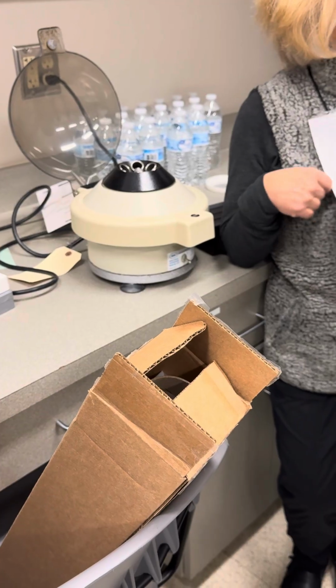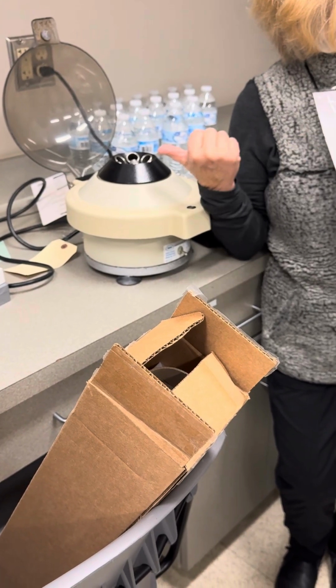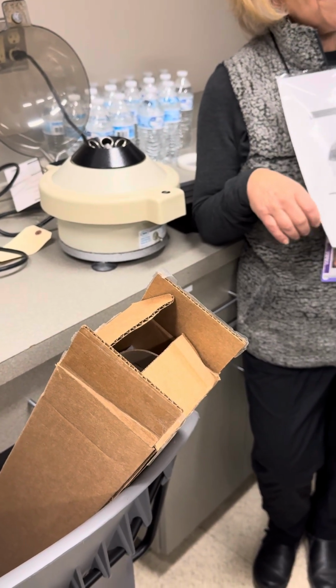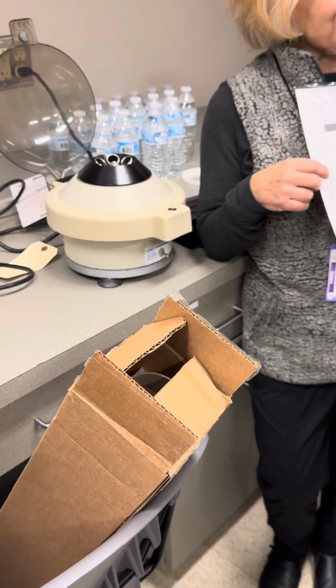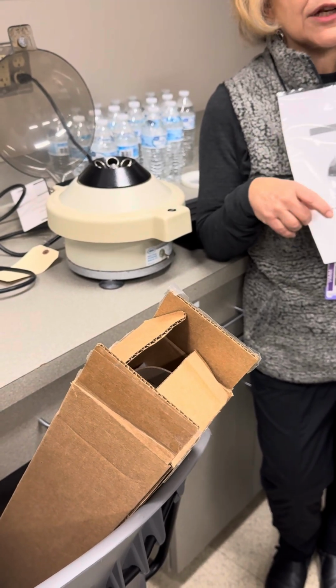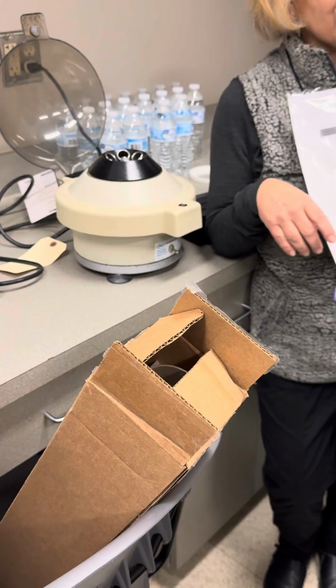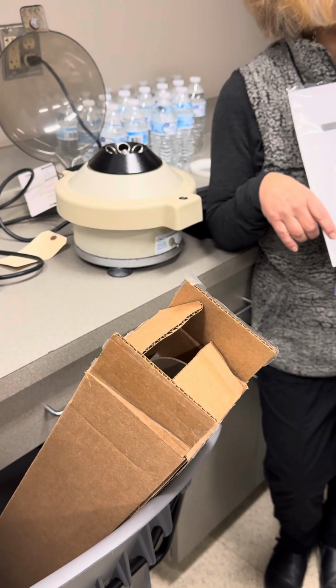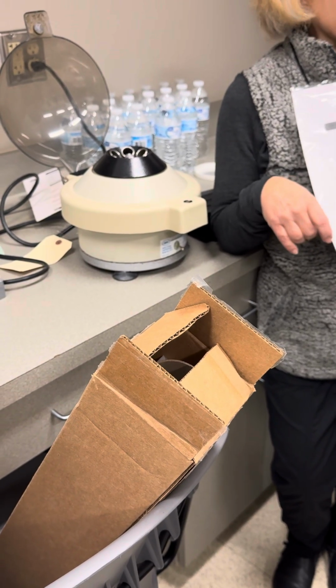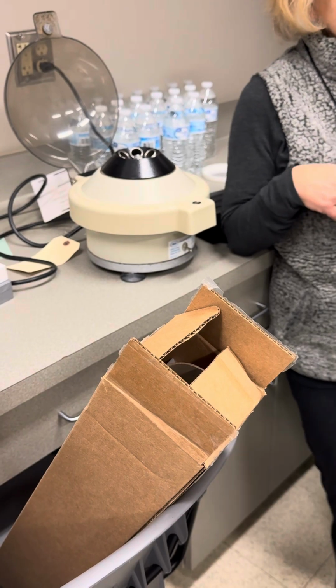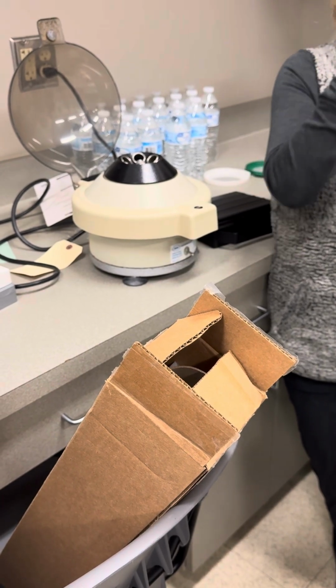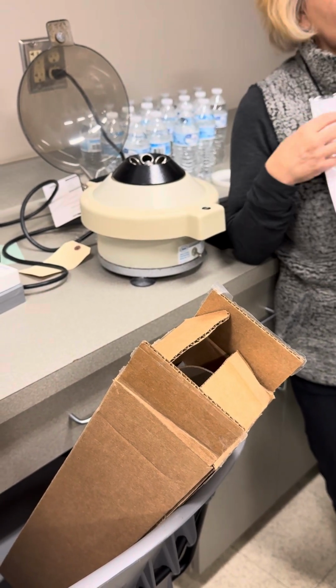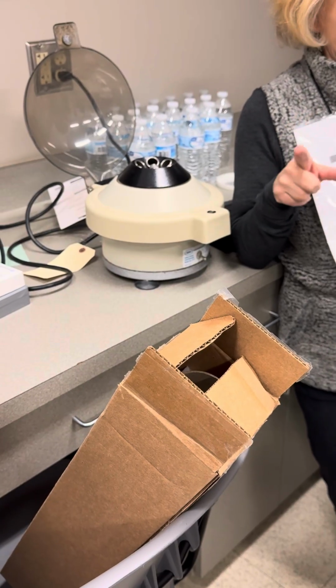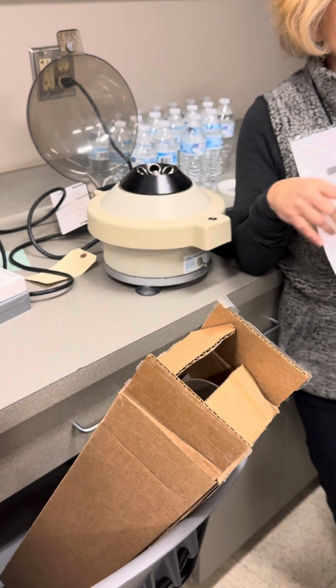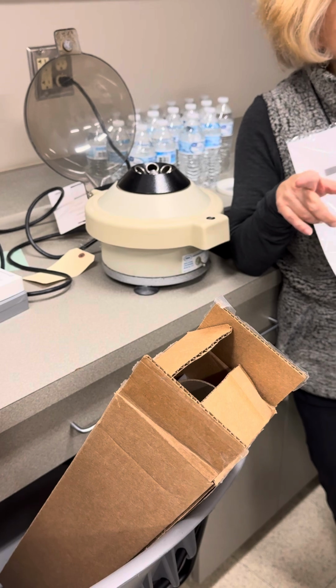And it will tell you what the RPM should be for that one. Commonly, as Greg has shared with me, it should be between 3,000 and 4,000. So somewhere around 3,500 RPMs per minute is what we're hoping for. Obviously, hematocrit machines, everybody's done a spun hematocrit, I'm sure. So those are 45, I think, but it's in the manual, and it'll be according to that, because the speed's much faster.